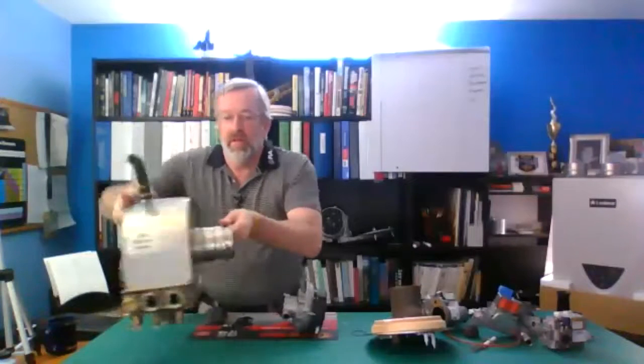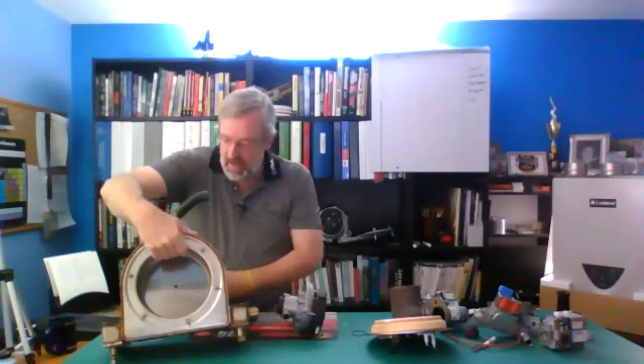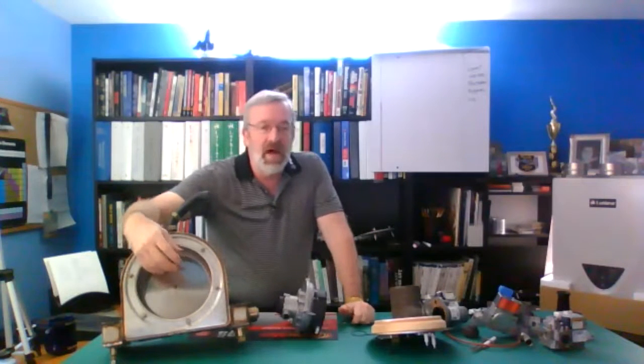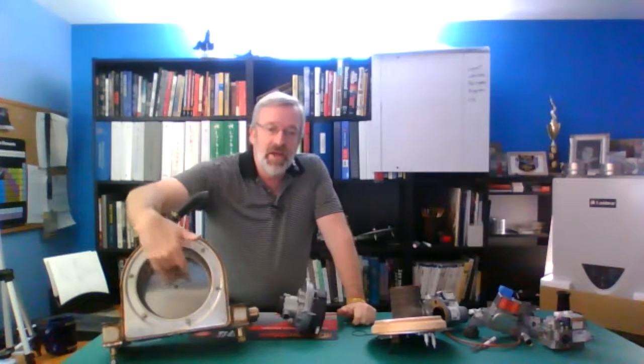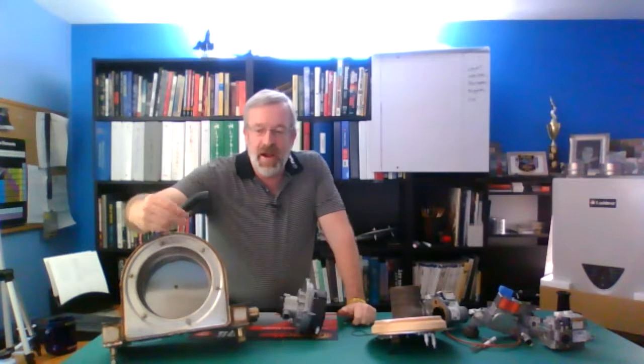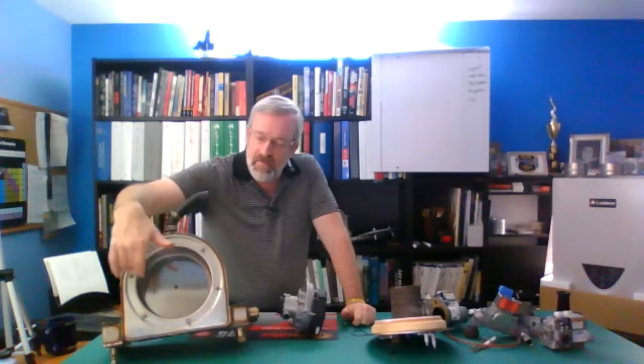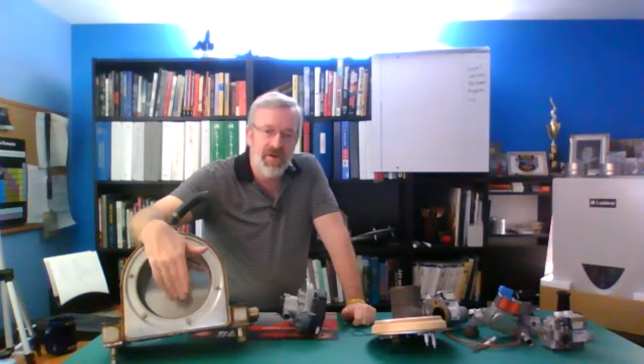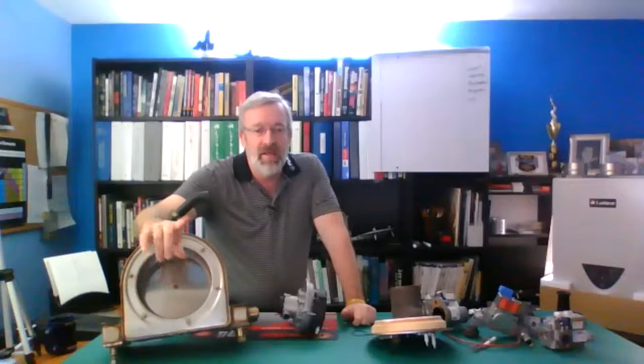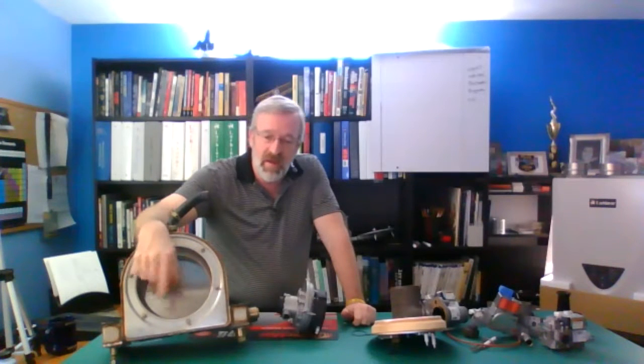Okay. So we want to make sure that we get clean in between these tubes so that we can get good air movement. And as I say, the nylon wheel does a good job with that. You could actually use a credit card, but if you have those old hotel key cards, you know, they're nice and smooth. You punch them down in there. If you have one that's really dirty, I'd start by vacuuming it out first. Then I want to hit it with that nylon wire wheel through there. And then I'm going to hit it with my vinegar and water solution, wipe it out, flush it down.